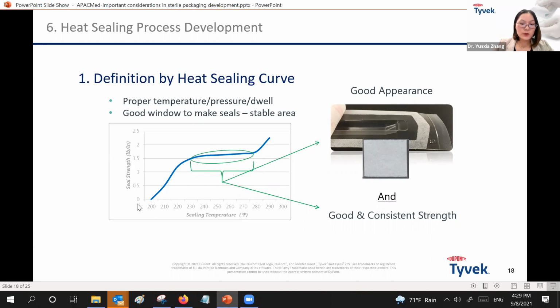So as you can see, with the increased temperature the seal strength is increasing, but there is a flat area. In this area, actually, is a good window to produce good seals and to make the seals stable. It will provide good appearance, seal transfer, and also consistent strength of the sterile packaging.